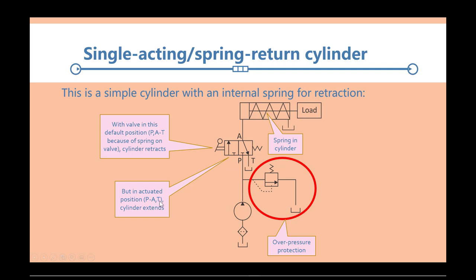In the actuated position, what you have is you have P to A comma T, so the T port then is not connected to anything, and P is connected to A, so the pressure source is connected to the actuation line going to the cylinder. And this valve is a three by two valve. We saw it before.